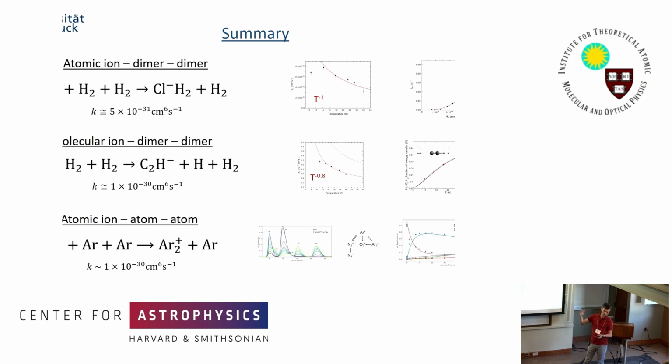It's usually not a good idea to cool all the way down and then heat up, because then you start to get rid of all the things that have been frozen on. So as we're cooling down, at the right moment, we turn on the heaters, and then it just stabilizes at that one temperature.